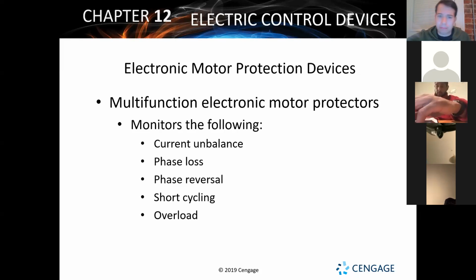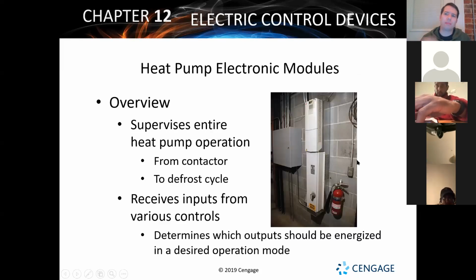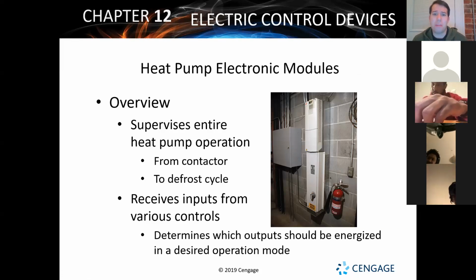All right. So like I said, basic number of things that it's going to control and look over and protect. The only other control that we're going to see a lot of, and y'all will get a lot of time with this when you take your heat pump class, you'll learn more about it, is your heat pump control module, or your defrost control board is what it's typically going to be referred to for the one specifically at the outdoor unit.